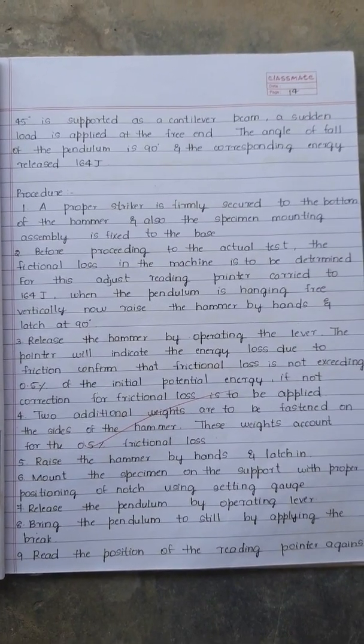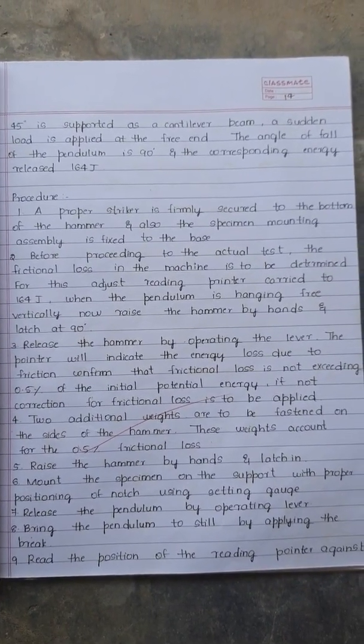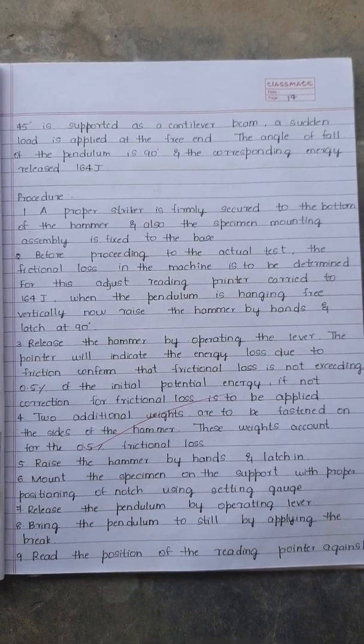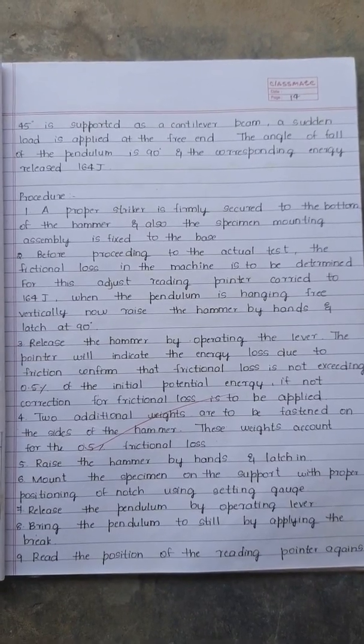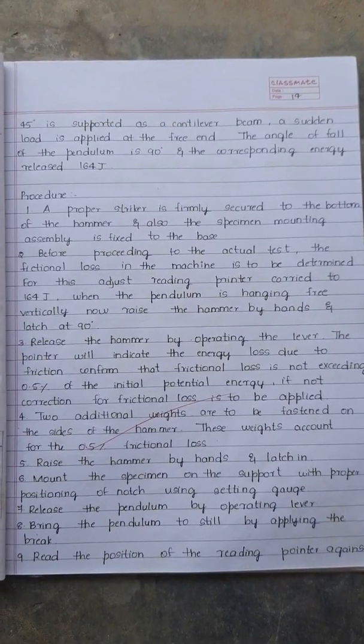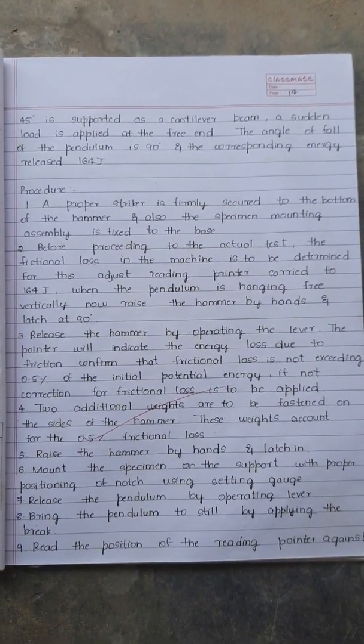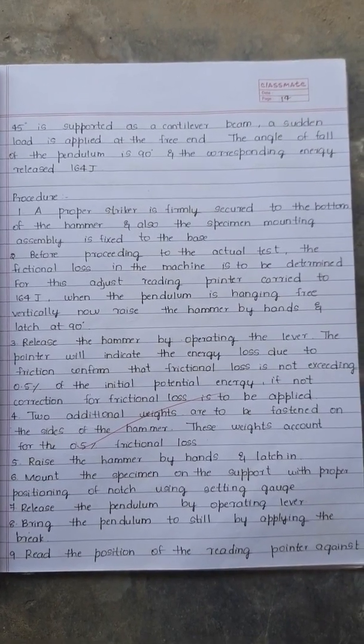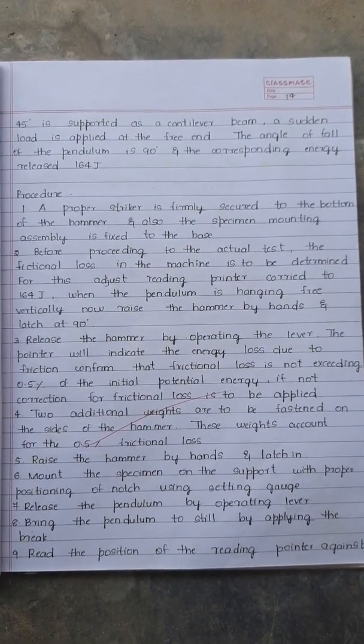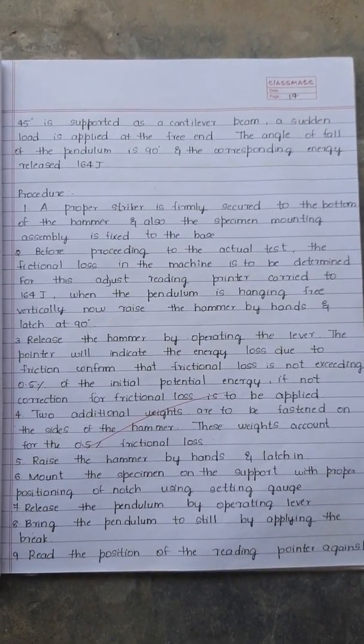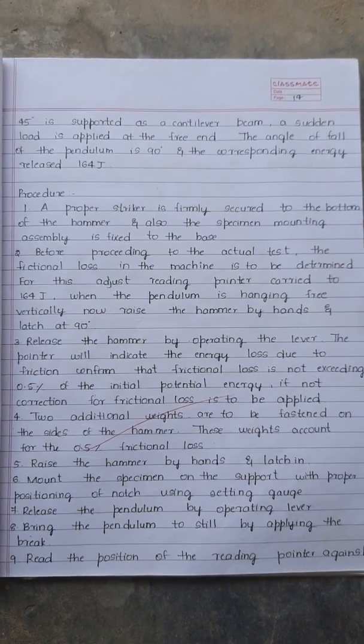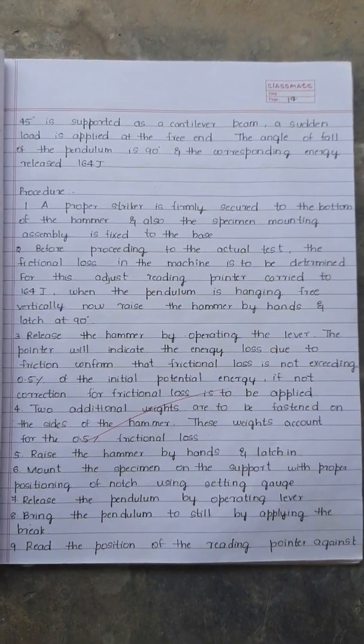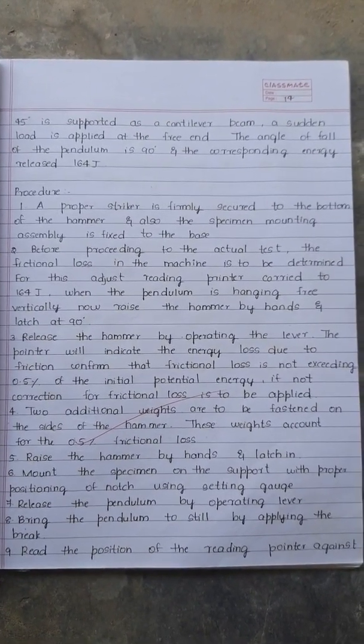Procedure: First, a proper striker is firmly secured to the bottom of the hammer and the specimen mounting assembly is fixed to the base. Second, before proceeding to the actual test, the friction loss in the machine is to be determined. Adjust the reading and correct it to 164 joules when the pendulum is hanging free vertically.